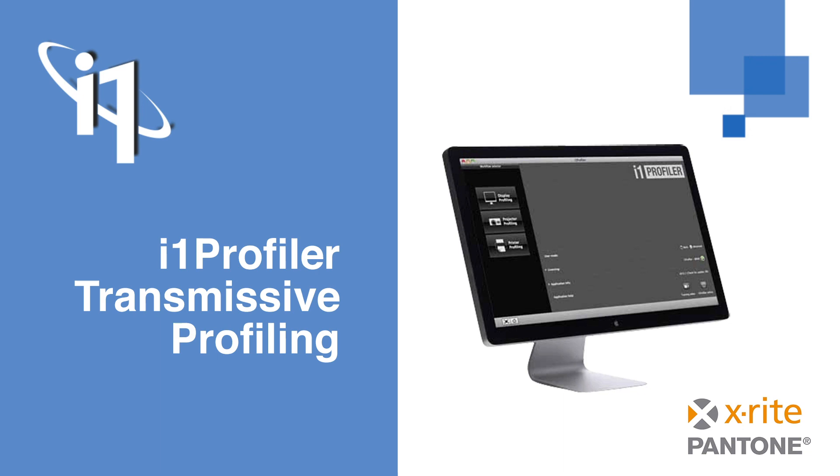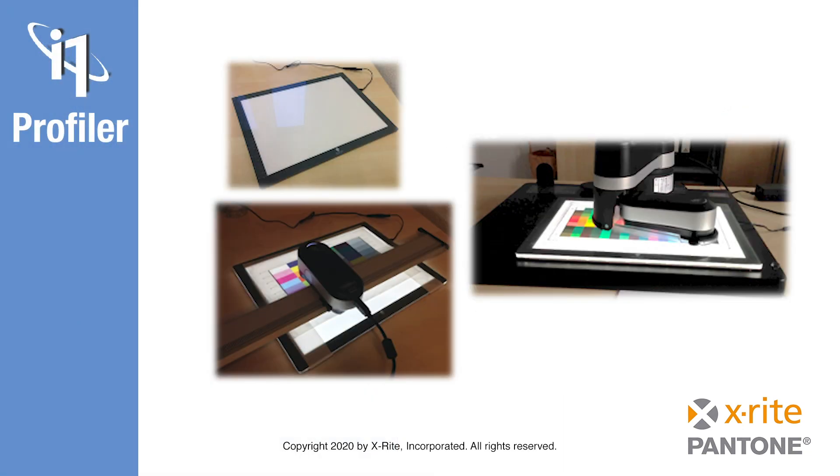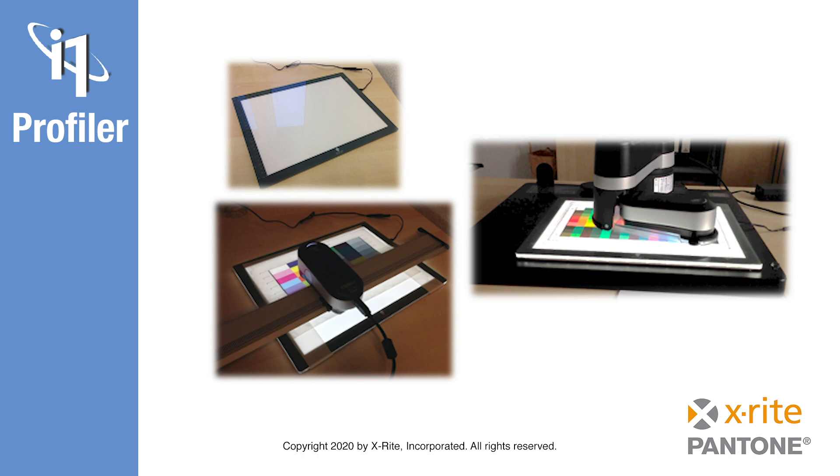To perform the transmissive measurements with either an i1 Pro 3 Plus alone or with an i1 IO3 table, a light box is required. There are a lot of light boxes available in the market which may be used. Preferred light boxes would have a color temperature range from around 5000 to 7000 Kelvin with consistent lighting across the entire measurement area.